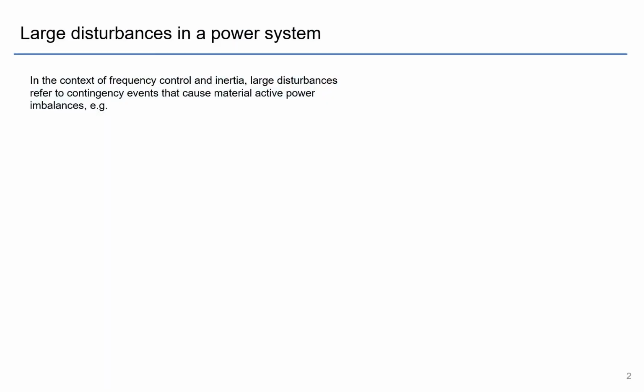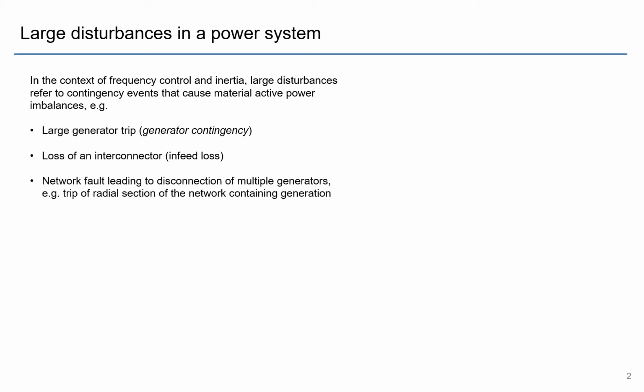So what is a large disturbance in a power system? In the context of frequency control and inertia, a large disturbance refers to contingency events that cause material active power imbalances. They could be a large generator trip, a generator contingency, a loss of interconnector, an in-feed loss, or a network fault that leads to the disconnection of multiple generators. So you might have a radial section of the network that has generation and you lose that.